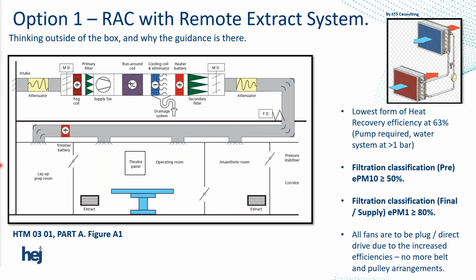So onto the air handling units then. So there's 4 options within HTM. And this method that I've got in front of you now is the least efficient method of heat recovery within the availability of the marketplace. If we go from left to right across the air handling unit, you can see that there's attenuation to our neighbours. As I mentioned before, sound management is important, and attenuation to the system. So we need to consider that when we're putting in test positions for the total traverse. Obviously, we can't drill into an attenuator. We just need to consider that as a designer.